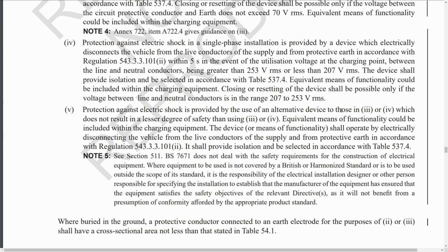So although it's a single phase in the property, the actual supply itself is from a three-phase supply, and because of course it's supplying many different houses, it's always going to be unbalanced because there's absolutely no possibility of those houses all having the exact same load at all times. So depending on the load you have in the various properties next door or across the street or wherever, if the PEN conductor is broken, the neutral point is not going to be central anymore. It is going to move in one direction or the other, and some of the properties may have a voltage outside of this range, either too low or too high, and this device would work.